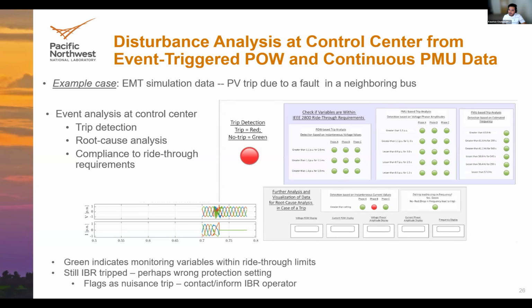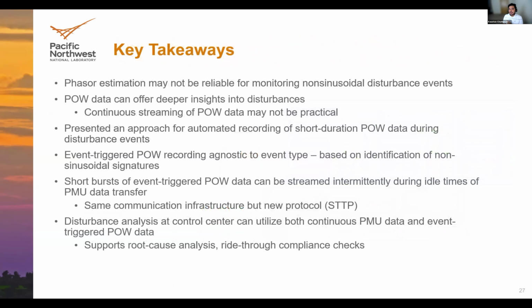Okay, so this is one of the use cases that I mentioned where we can use high resolution point on wave data. With that, I will conclude my talk. The few takeaways are that phasor measurements are not always reliable for monitoring non-sinusoidal disturbance events. To complement that, point on wave data can offer deeper insights into disturbances. In that context, continuous streaming of point on wave data may not be very practical. So we talked about an automated approach for recording short duration point on wave data for disturbance events.